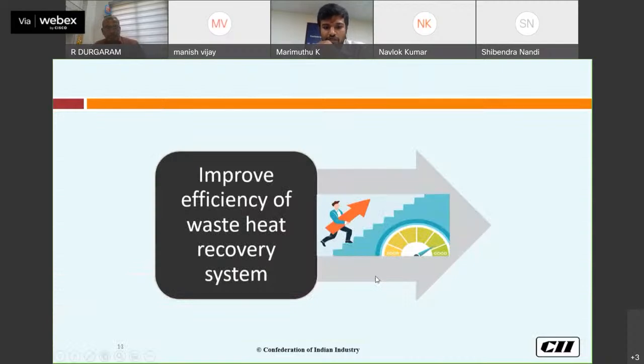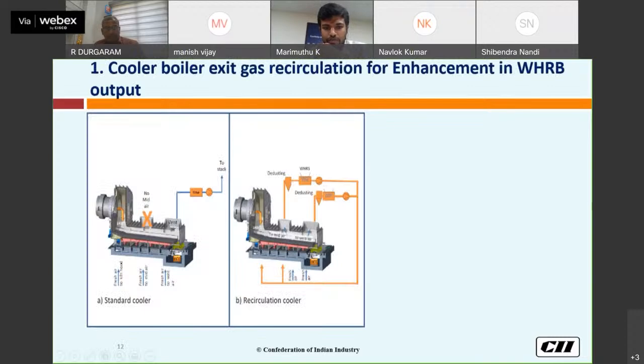Then coming to improving the efficiency of the waste heat recovery system. The first one is about cooler boiler exit gas recirculation for enhancement in WHR output. The left figure gives the idea of a normal cooler without any recirculation, and the right side figure gives the process diagram with cooler air recirculation to the WHRB plus vent air, meaning stack air recirculation.